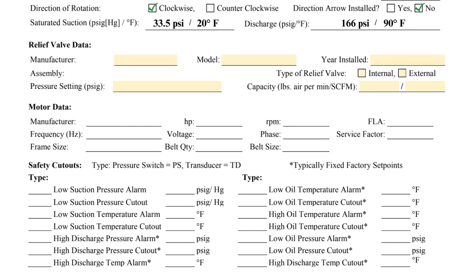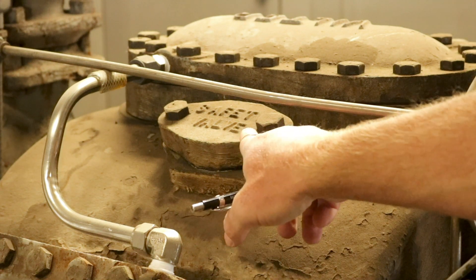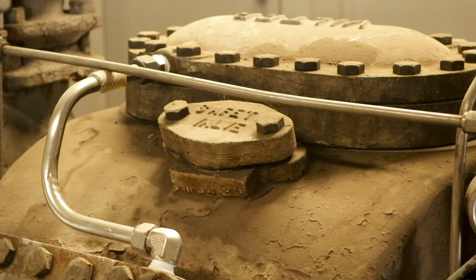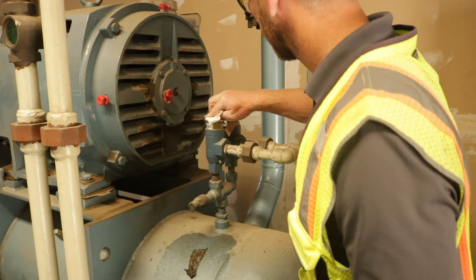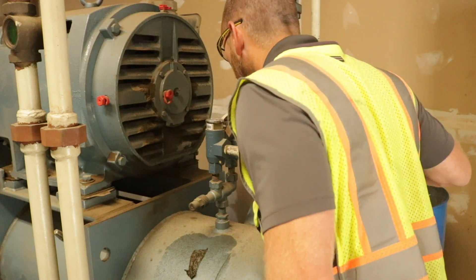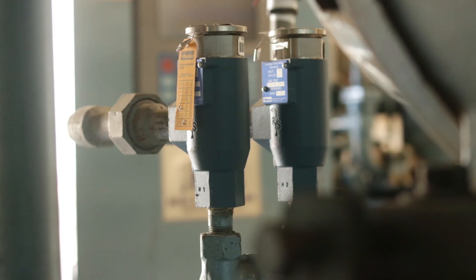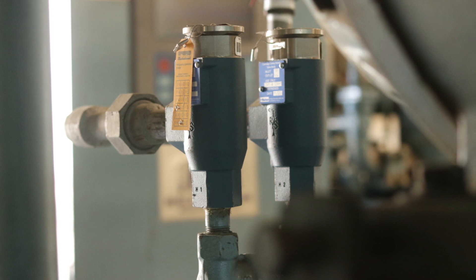The next section is named relief valve data. The reciprocating compressor is protected from overpressurization using an internal safety valve, so that should be indicated and the other fields in this section are not applicable. For the screw compressor, information such as the manufacturer, model, pressure setting, and capacity can be obtained from the relief valve nameplate.